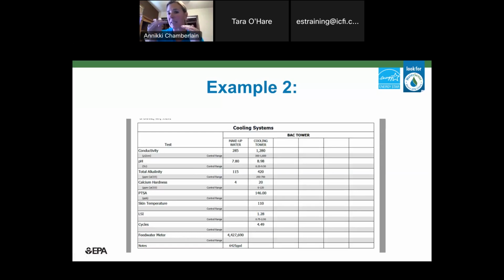I can start understanding, even just quick brain calculations. I can start seeing, okay, what am I looking for as far as cycles of concentration? So they've got some good ranges: what the water coming in is, the water going out. They've got some ranges of what's acceptable. So this is quite a bit of information in here. They've calculated the cycles here off of conductivity. So this is pretty good. I'm not exactly sure what our optimal is, but honestly, once I see 4.5, I'm pretty good.